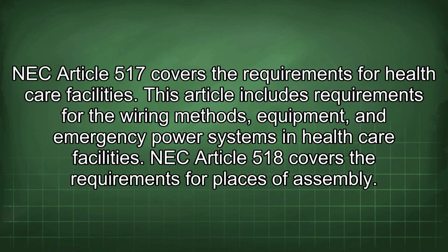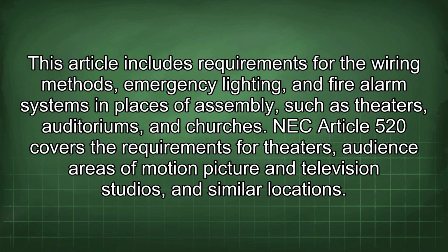NEC Article 517 covers the requirements for healthcare facilities. This article includes requirements for the wiring methods, equipment, and emergency power systems in healthcare facilities. NEC Article 518 covers the requirements for places of assembly. This article includes requirements for the wiring methods, emergency lighting, and fire alarm systems in places of assembly, such as theaters, auditoriums, and churches.